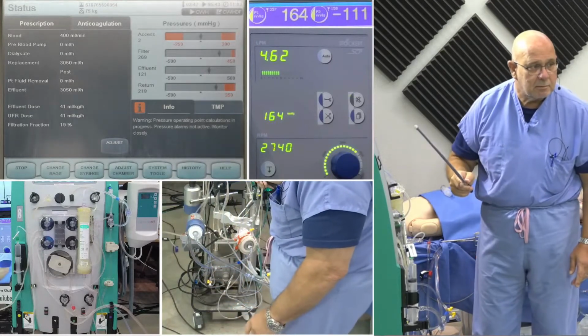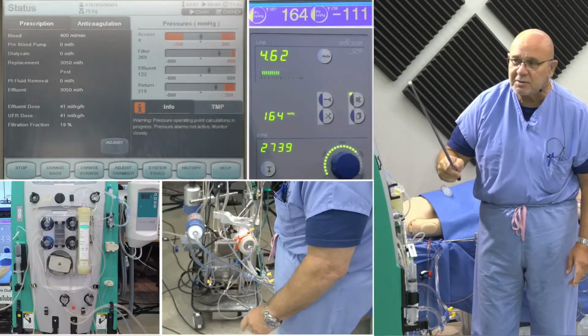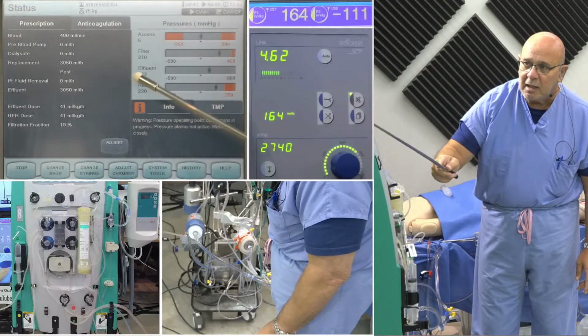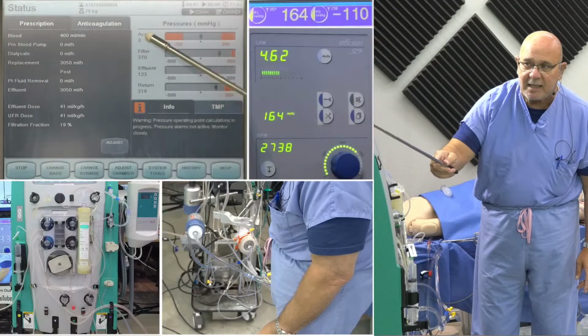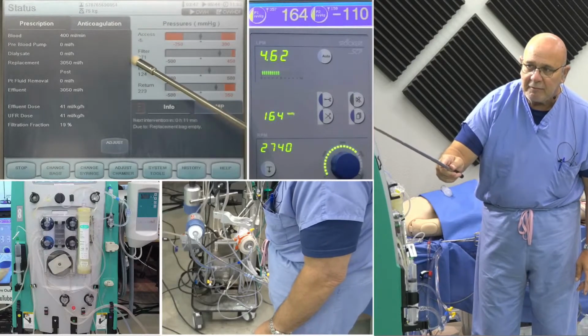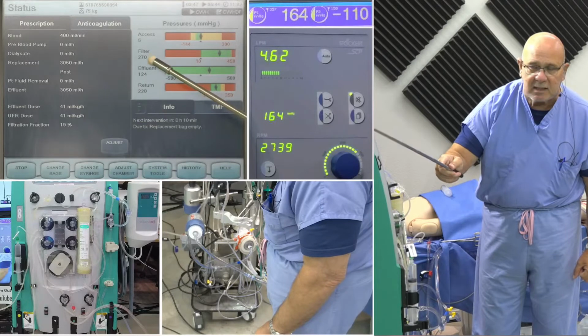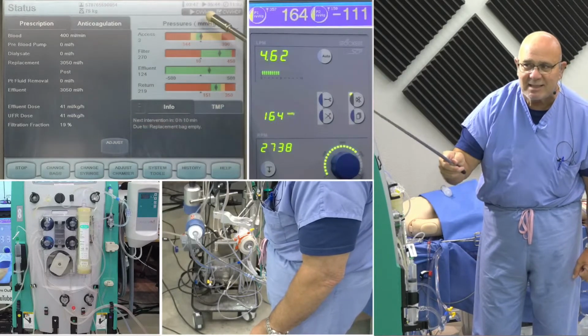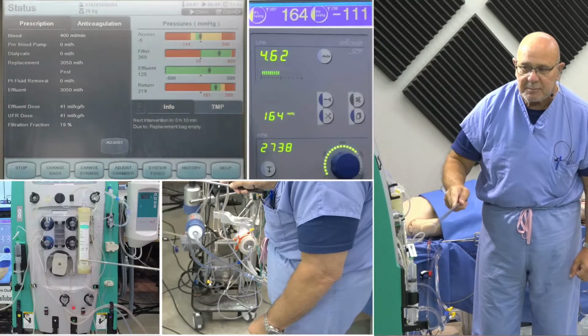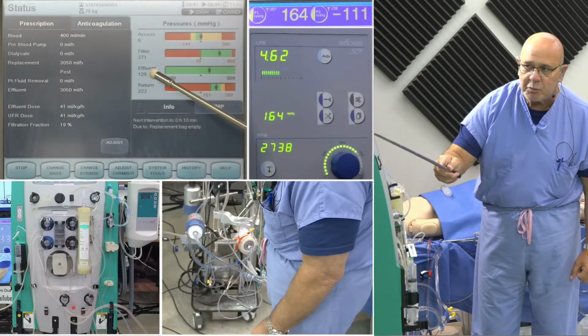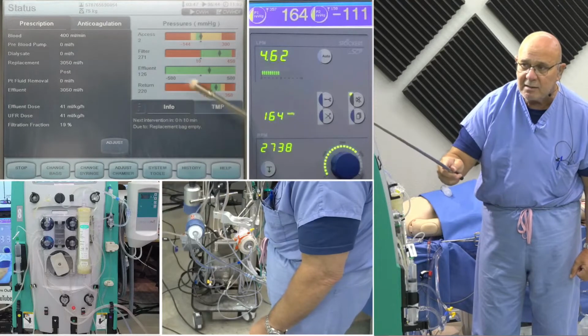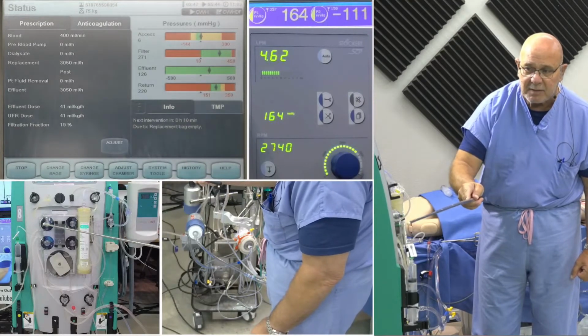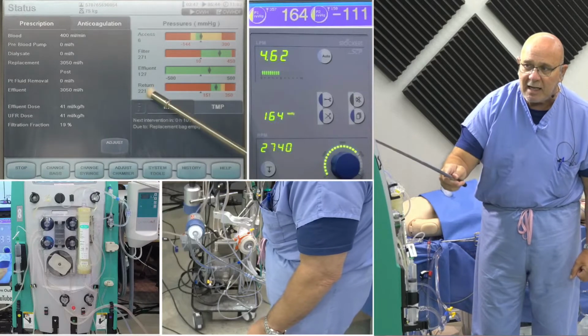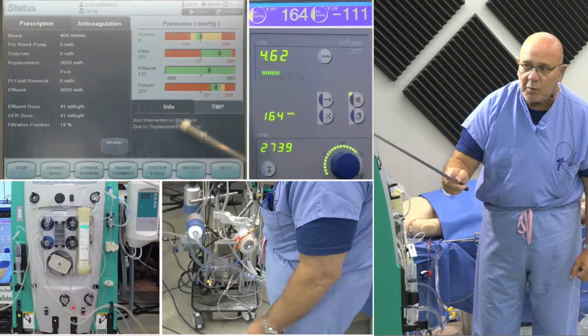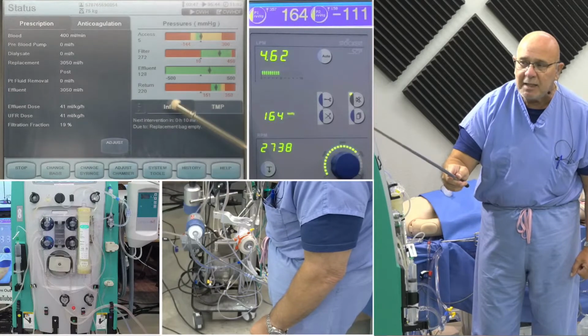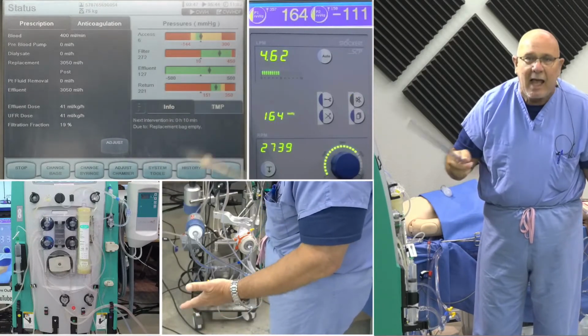Like this? That good? Oh, I'm sorry. Okay. Our access pressure is positive. It should be negative, but this doesn't hurt anything. Our filter pressure is 270. That's a little high, but that doesn't hurt anything. That's resistance. That's not because the filter is being clogged. Our effluent pressure is 125, which is great. It's very positive. This effluent pump is acting as a dam, and our return pressure is 220. Again, maybe a little bit high, but not anything bad.